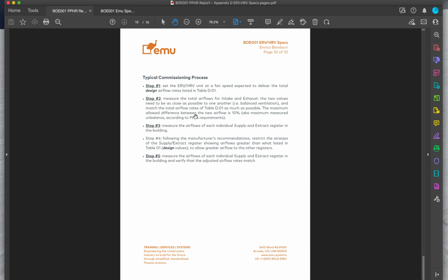You do in the next document. We're gonna see how we spec as part of the preliminary passive house review. We make recommendations as far as where to locate individual registers in interior rooms, and we spec the supply rate or extraction rate for those individual registers, and those airflow rates need to be commissioned and delivered, and that's something that the ERV or HRV cannot control, so that's something that needs to be manually commissioned. So that's why we went the extra mile and added indication on how to commission the system.